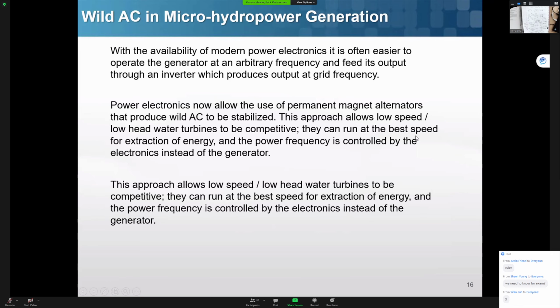So in this case, even if your generator cannot run at a very high frequency, you still will be able to use the power they generate. So that's why they said they can let them run at the best speed for actual extraction of energy. The power, the frequency, and the voltage are controlled by those power electronic devices instead of the generator. So that's why we consider them the best for any type of situation, not only in the wind turbine.